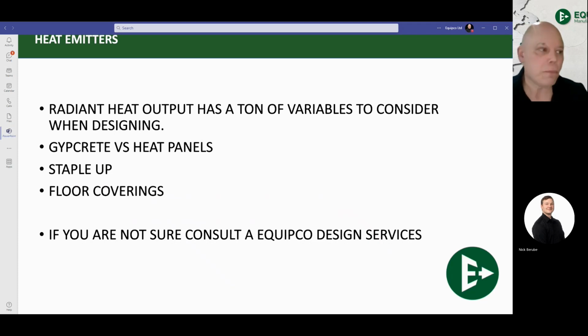Which leads you to the last point, floor coverings. Carpet is going to require a hotter water temperature and a hotter floor temperature than, let's say, tile. And tile, similar to hardwood, is going to have a maximum floor temperature that you can get it to without damaging the tile or warping the hardwood. There are, again, so many variables with radiant that I highly encourage and strongly recommend that when you're doing a radiant system, get that one designed. Don't just guess at that one. If you do, you can do more damage to a system than good by overheating it and cracking tiles and warping floors, and the homeowner wouldn't have any idea what they're in for. So just make sure that you're as aware and educated as you can be on radiant systems, and then do a little bit of work with the contractor and homeowner as well.